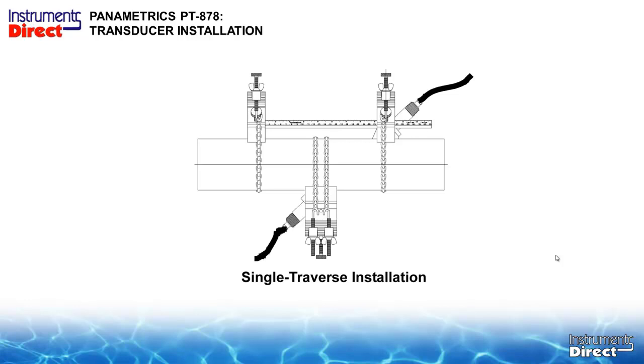Here's a picture of the single traverse, so we're going to put the standard clamp on one side of the pipe, and then we're going to put the single transducer on the other side of the pipe. And on a large pipe application, this can actually be lots of fun, because sometimes you can't see the other side of the pipe. So my suggestion is to put the track on one side of the pipe with the ruler and everything, mount it, and then draw a line up to the other side of the pipe and measure 180 degrees, draw another horizontal line, draw a line across the top of the pipe from the starting position of one transducer and put a transducer on the mating side.